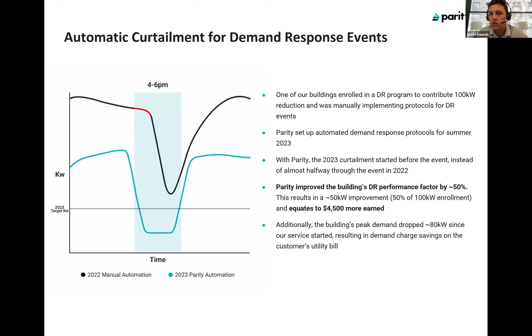For any hotel engineers on the call with experience with demand response, it can lead to a lot of manual running around the building making manual adjustments, which on a very hot day you really don't want to be doing. Through automation, you can triple, sometimes more, the amount of revenue you're generating, and do it in a way that's really measured—sitting at your computer, and if you feel like you need to ramp things back up so you don't lose the thermal situation in the building, you have the ability to do that through automation.